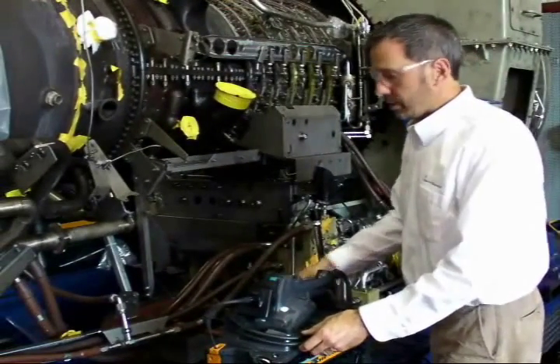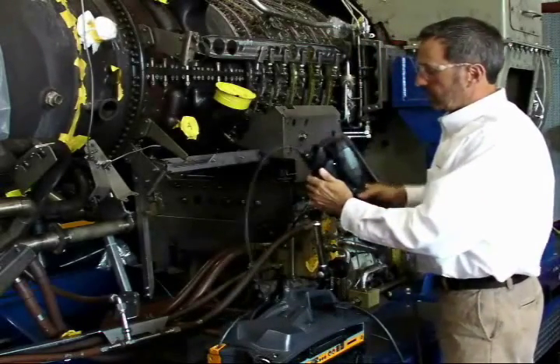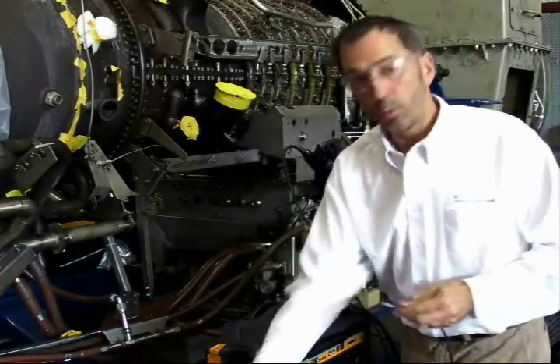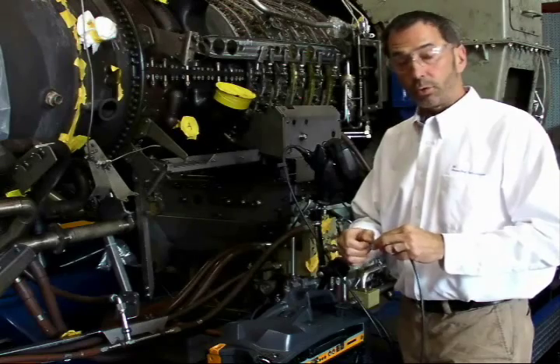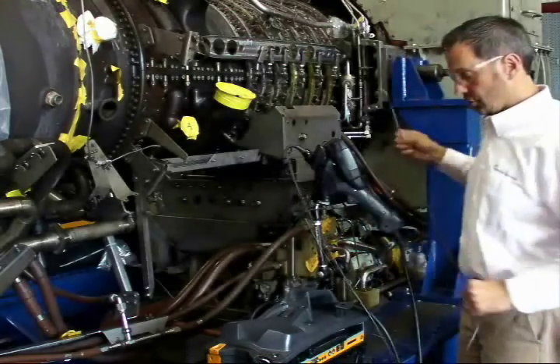Using the 3D Phase Measurement System for the XLG3 saves time during an inspection. The system has automatic tip detection, so once you attach the measurement tip it's automatically detected for either forward or side view and it's ready to go. You just start your inspection.